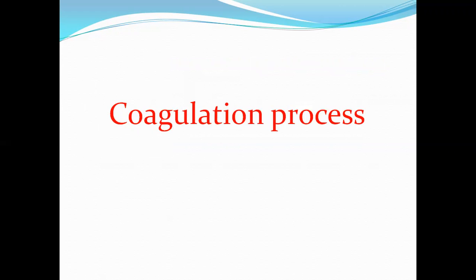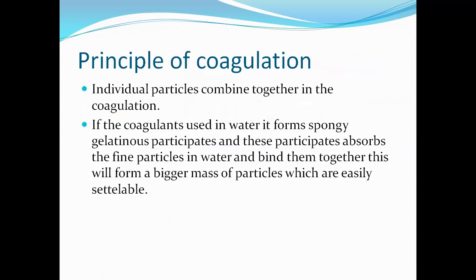Now see what the coagulation process is. The principle of coagulation is that individual particles combine together — that is, two or more particles combine to form one particle. If coagulants are used in water, they form spongy gelatinous precipitates, and these precipitates absorb the fine particles in water and bind them together, forming a bigger mass of particles which are easily settleable.